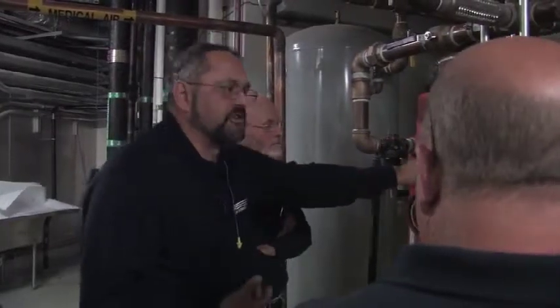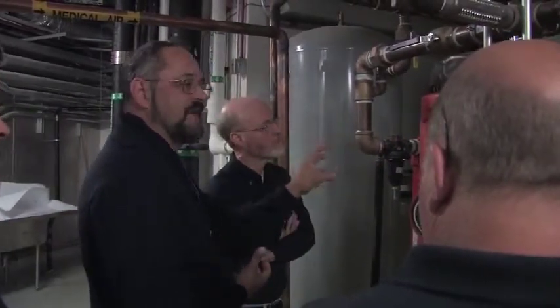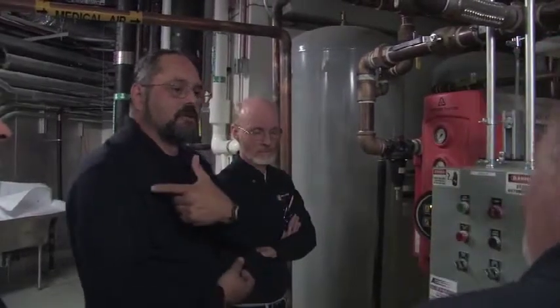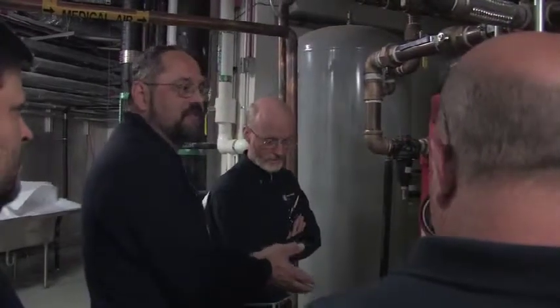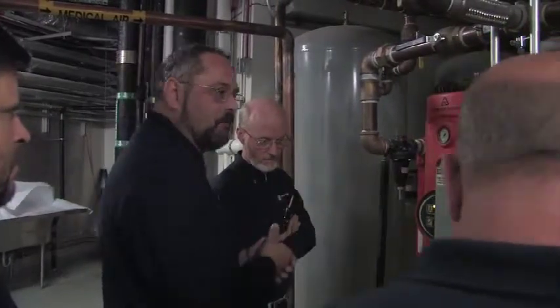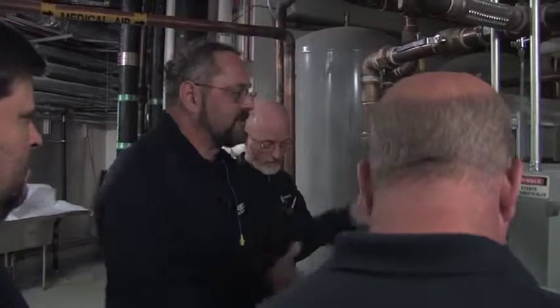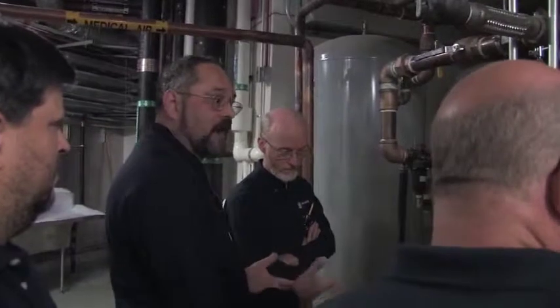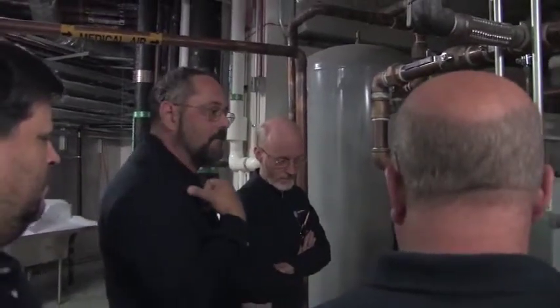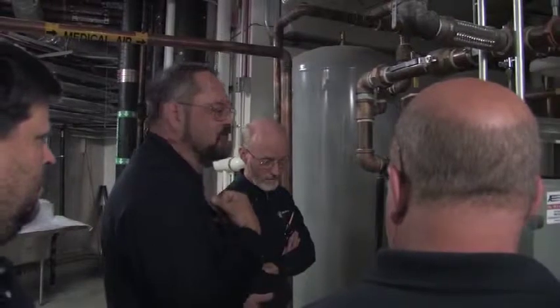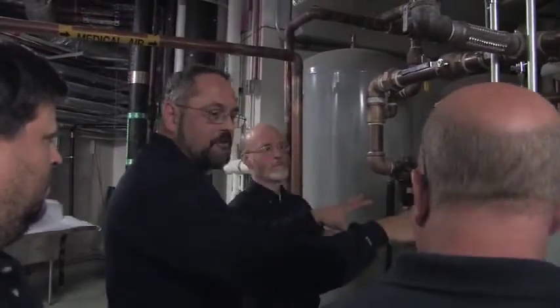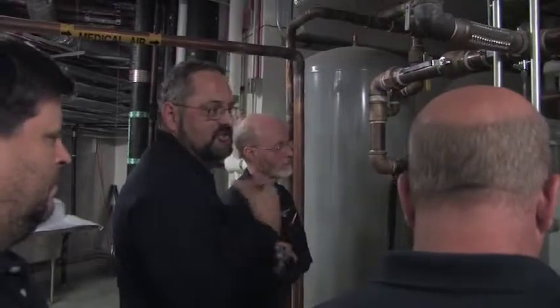Again, if this purges, it purges 15% of its full capacity. So if its full capacity is the output of 2.5 of those compressors, the purge out the muffler is 15% of that total cubic feet. So if we put both dryers on, we could end up using half the output, and we left it like this without the purge saver. Right. We might end up with a minus 80 dew point on both dryers. But the other thing we'd also end up with is we probably have one compressor running 50% of the time just to make the purge. And that's obviously electricity, it's energy, it's wear and tear, it's maintenance.